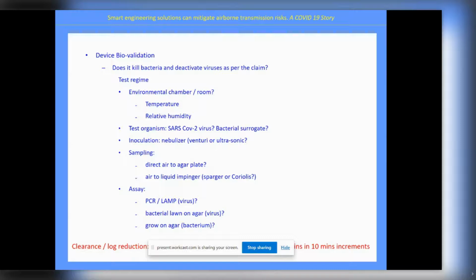Inoculate the room, this large room, with a nebulizer, a Venturi system, ultrasonic, stir it all up with lots of fans, then sample the air as the device runs over an hour to estimate the clearance rate. Sample onto an agar plate so these bugs can be grown, or sample the air into a liquid and then sample the liquid into vials, which then can be looked at by the microbiology lab. What assay can we use? Well, we can use PCR or LAMP for the virus, in theory. If it's a virus, we can challenge bacteria on an agar plate, or if it's a bacterium, we can simply grow it on a plate.